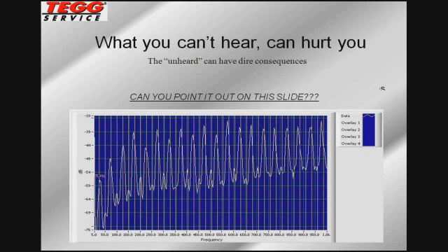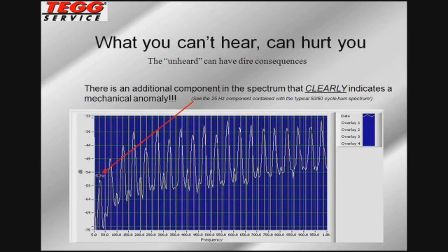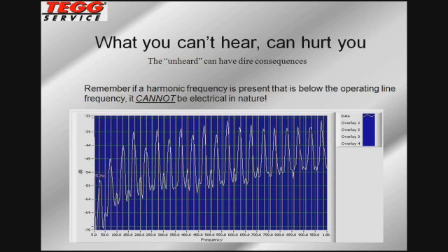What I'll say about that particular frequency, number one, is that it is below the line operating frequency. Over in the United Kingdom, the power systems operate at 50 hertz. If you have a true electrical anomaly, whether it's 50 or 60 hertz, and you see a fault frequency like this that is below your operating frequency, it immediately rules out anything electrical. It's impossible to have a frequency like that on the spectrum if it's an electrical issue. This indicated a mechanical type problem, and what it ended up being was a nameplate where a rivet had come loose on the transformer and was vibrating, and it produced this spectrum. So it won't be electrical in nature if your fault frequencies are below your line operating frequency.